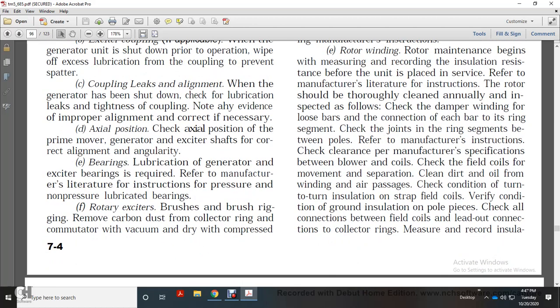Alright, your rotor windings. Rotor maintenance begins with measuring and recording the insulation resistance before the unit is placed in service, referring to manufacturer literature instruction. The rotor should be thoroughly cleaned annually and inspected for fouling. Check the damper winding for a loose bar or connection, each bar of the ring segment. Check the joint with the ring segment between poles. Check the clearance of the air gap per manufacturer specification between blower and coils.